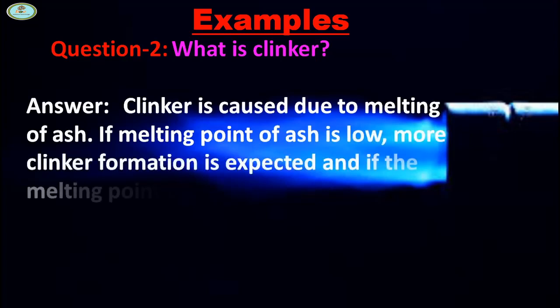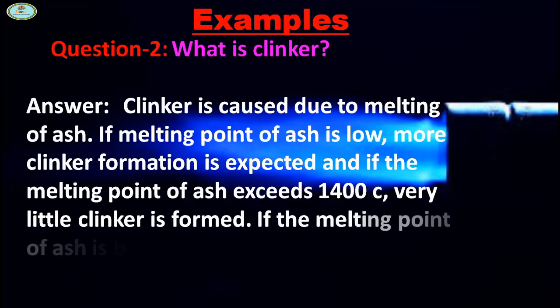Clinker is caused due to melting of ash. If the melting point of ash is low, more clinker formation is expected. If the melting point of ash exceeds 1400 degrees Celsius, very little clinker is formed.